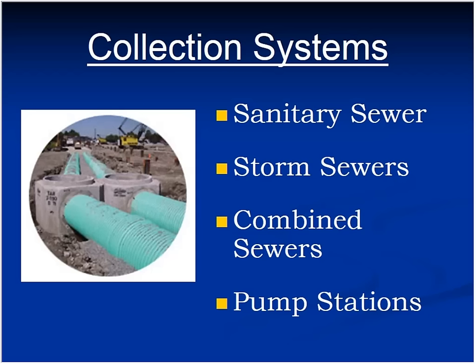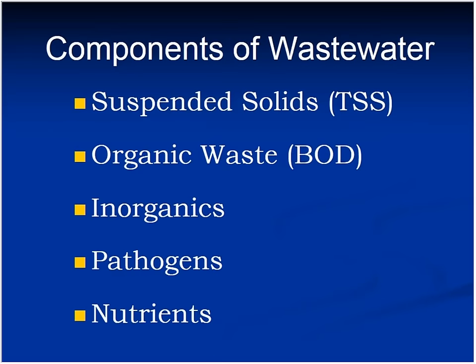We also have pump stations. We're not living in flatland Illinois. Got to get over the hill, so we've got pump stations out there to help get us over those high points. When we look at what's in there, the two major components that we deal with are biochemical oxygen demand, BOD, and total suspended solids, TSS. In the initial NPDES permit, these limits were set at 30-30. Those were the two prime things that they were out to reduce.